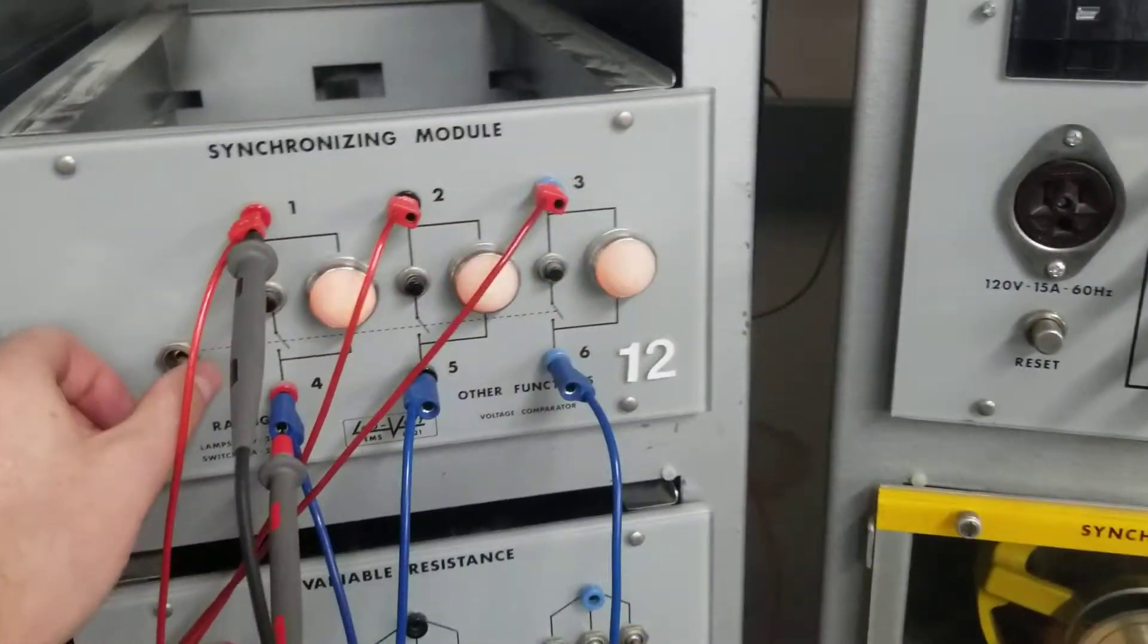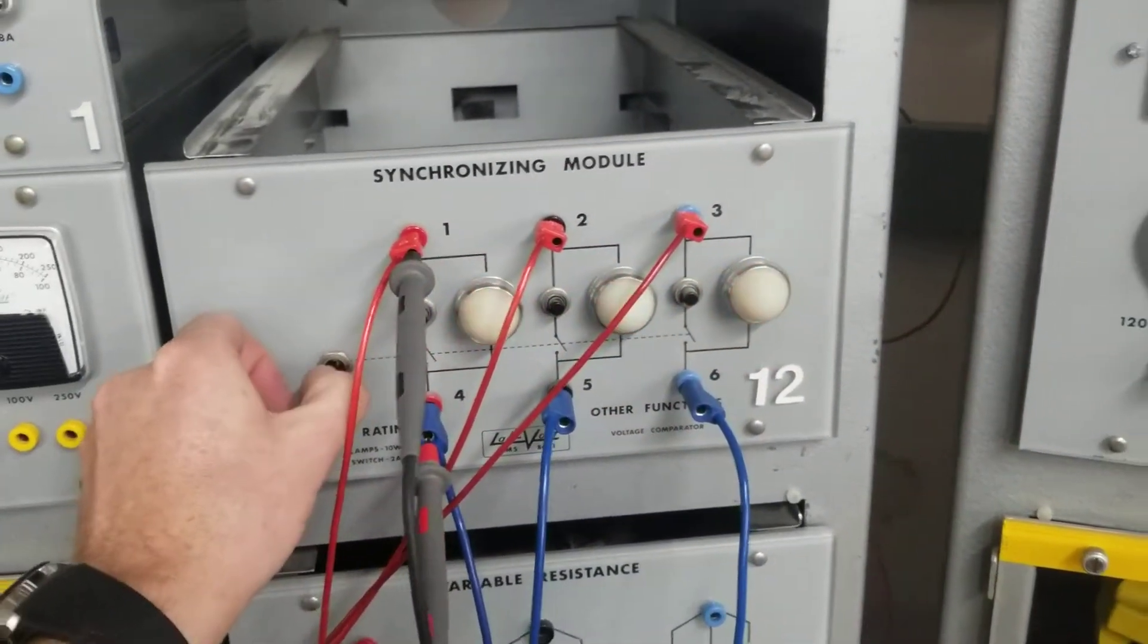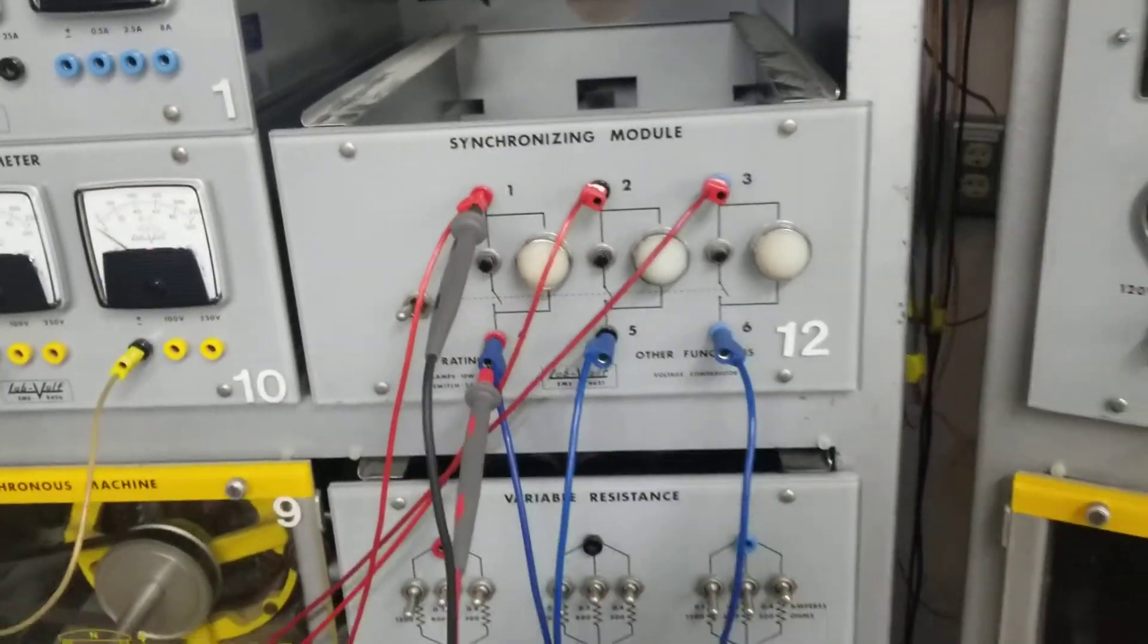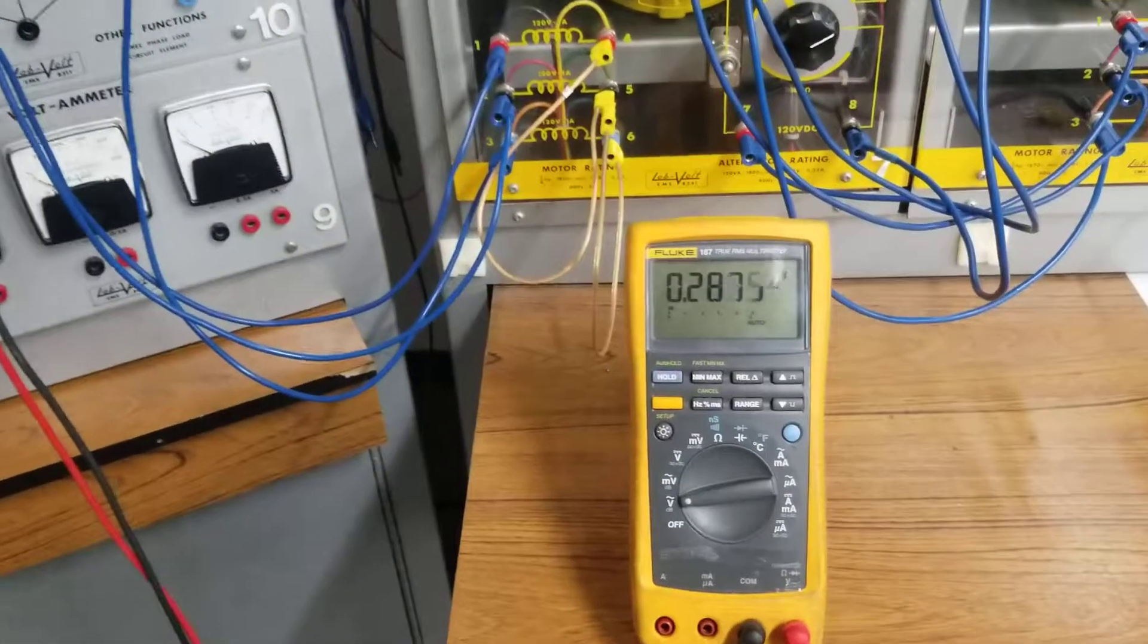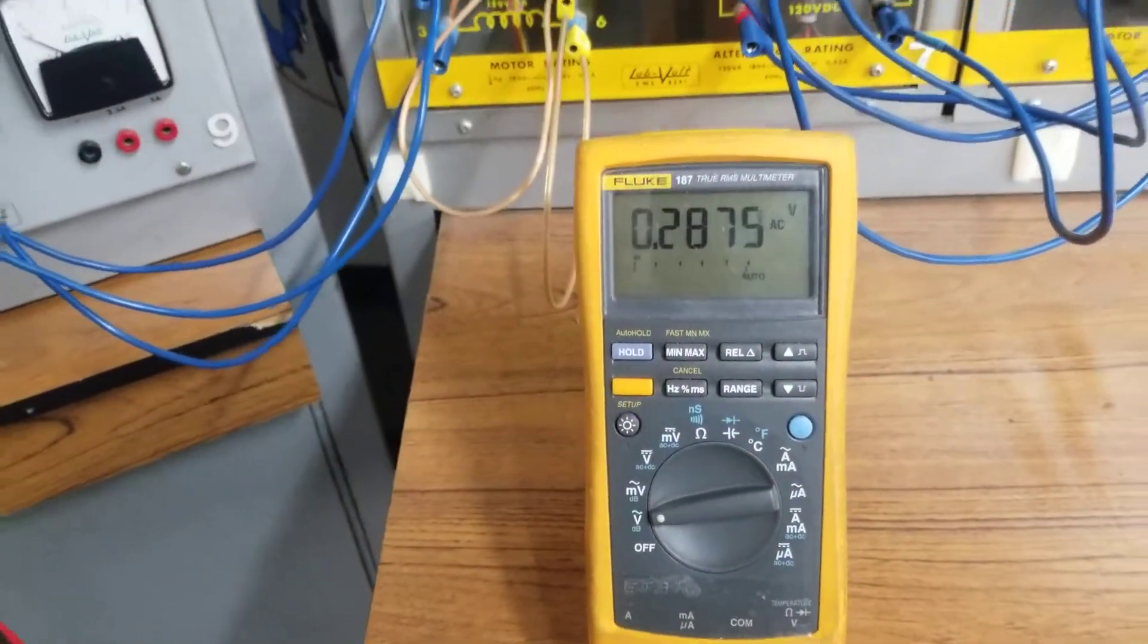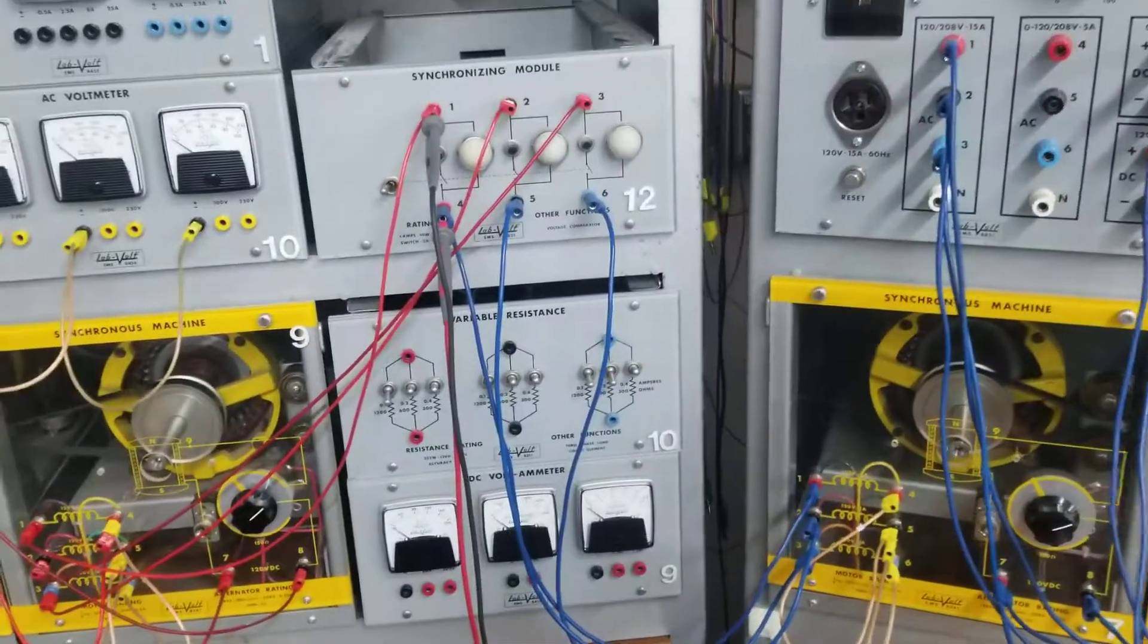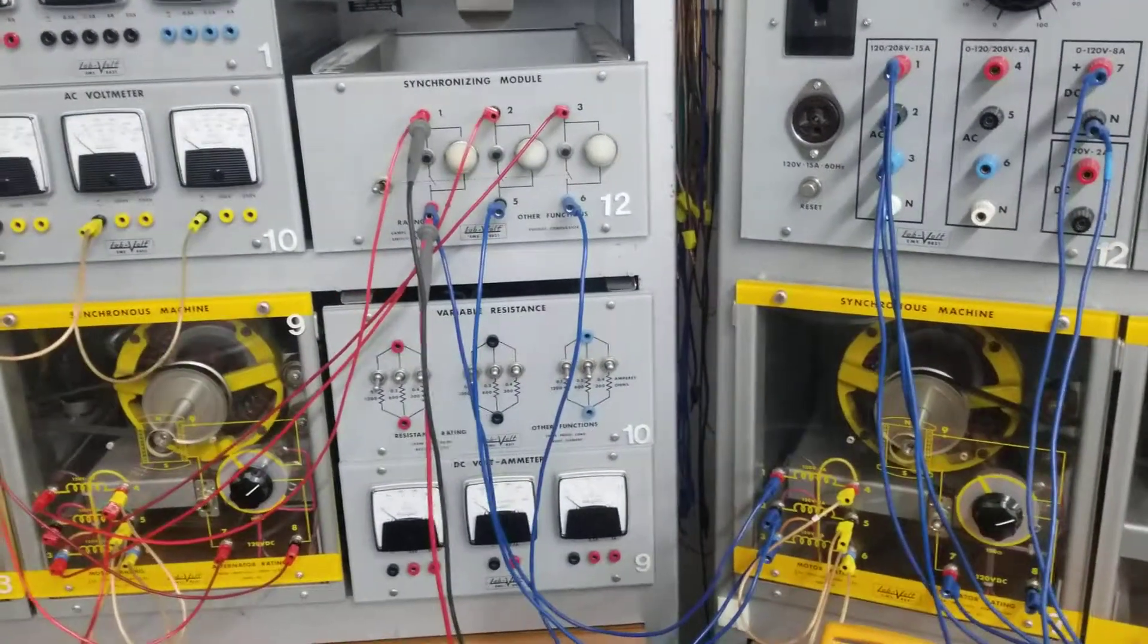As soon as the lights go dark, that's when I flip the switch. Now both machines are locked together. And that's why you're getting zero volts, which essentially means you're getting zero potential between each generator.